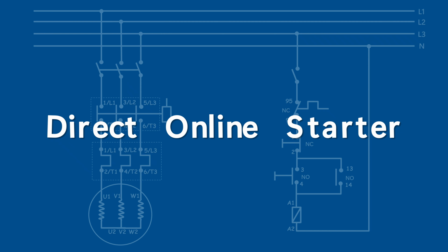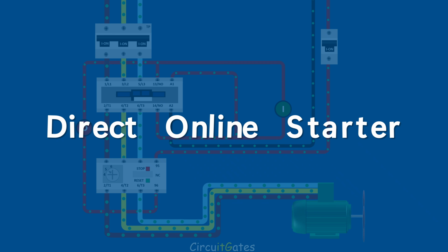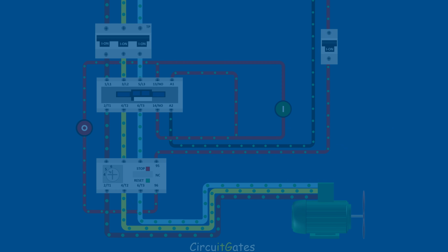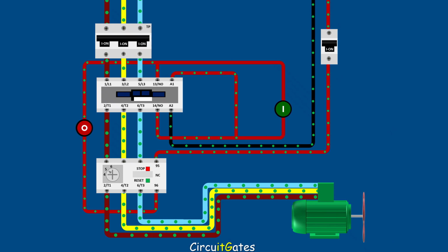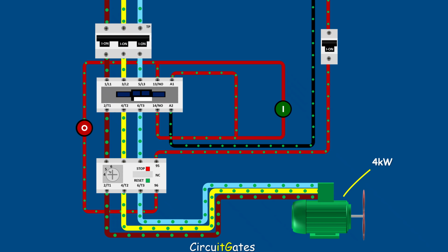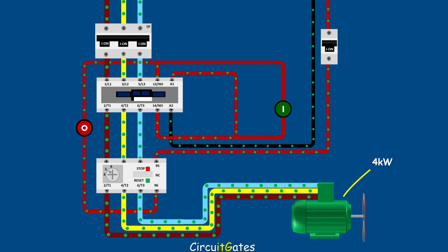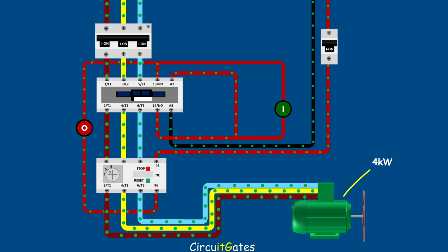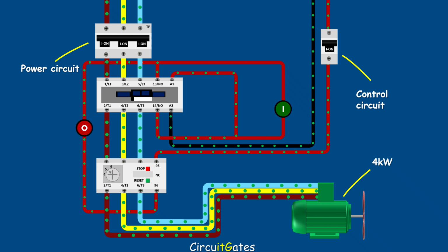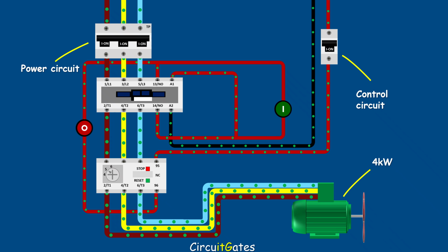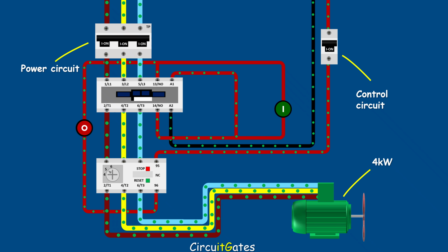Hi guys, in this video we'll look at how a direct online starter works. A direct online starter is a method widely used in industrial sites to start small induction electric motors, typically of 4 kilowatts or less. The direct online starter has two circuits, the power circuit and the control circuit. The power circuit provides power to the electric motor, and the control circuit controls the operation of the electric motor.